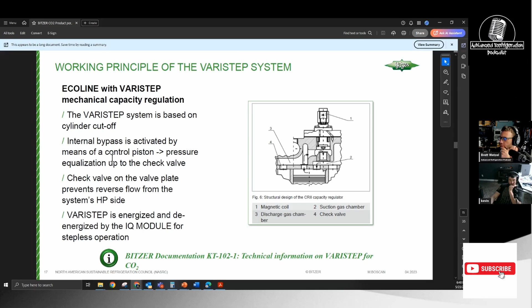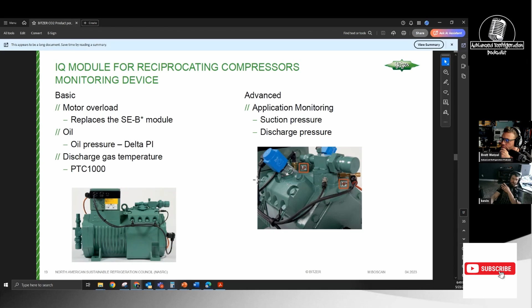Yeah, so like I said, low pressure, high pressure. You said that one had liquid injection. Where are you putting the liquid injection on this bad boy? So this one, the OEM had it going into the suction. Oh, so it was already pre-done. Yeah, I didn't mess with that. I just wired the coil into the liquid injection pulse. Gotcha.